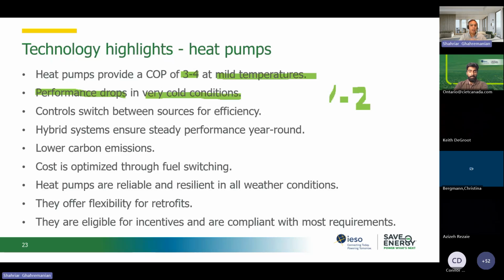There are different types of controls. If we have hybrid heat pumps, then because these days we need to survive a cold winter season, a hybrid system is necessary, or we invest in cold climate heat pumps, either of them. These days, the hybrid system is more popular, which means that different types of controls are available depending on the control strategy. That system shuts down the heat pump and turns on the auxiliary or backup heating system, and it runs that until the control decides to go back. Again, the heat pump still has lower carbon emissions. The cost can be optimized through fuel switching, so it's a good one. It's reliable, resilient, and it works. They offer a lot of flexibility for retrofits, and there are also incentives.